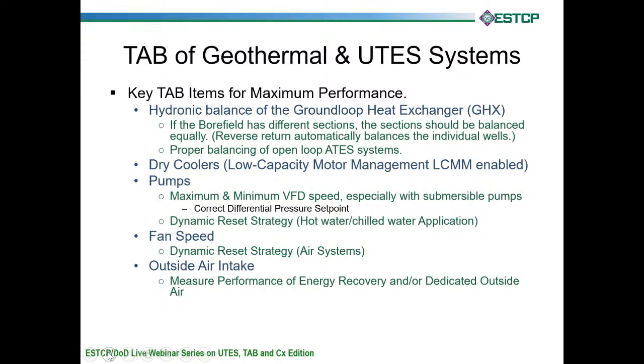Another key TAB item that some balance contractors may not think of has to do with the dry coolers on a UTES system. We've talked about dry coolers in our previous webinars, and some dry coolers that we've run across have different features for energy savings, like low capacity motor management, which is known as LCMM, and that allows the fans to stage on and off and speed up and slow down to meet the load. Sometimes dry coolers that we've seen don't have that enabled, but it is available, and it just has to be set up by somebody, and most of the time that somebody needs to be the TAB guy.